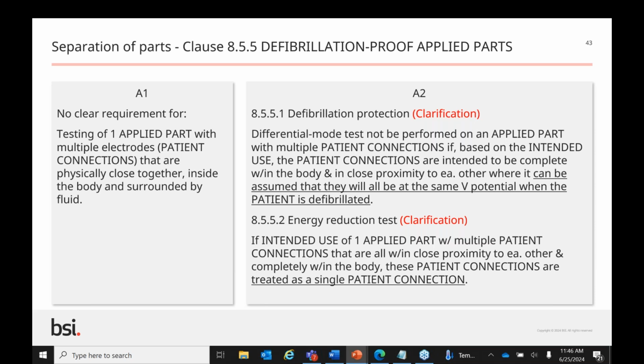I had a client with this issue as noted in A1. There was no clear requirement and the client dealt with a lab that provided them with failing results. The lab didn't know how to test it because there really wasn't clear requirements for the situation. Finally, the lab agreed it was not being tested properly and we came to a solution, but it was a long, drawn-out battle. It wasn't a top lab either. This all spurred a request for a change, which I submitted for the issue for the 601 standard, but it took many years before the changes occurred through the standards process for the amendments project.